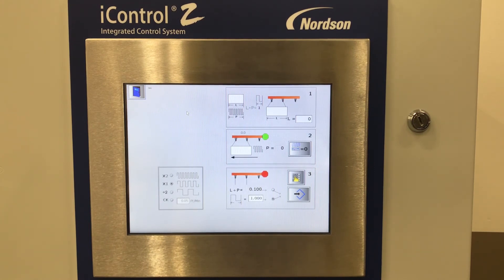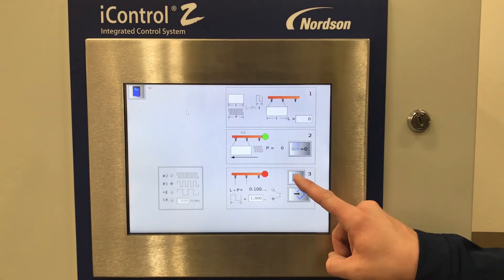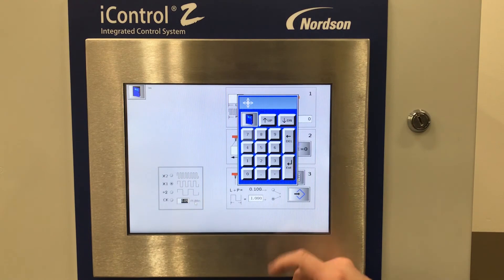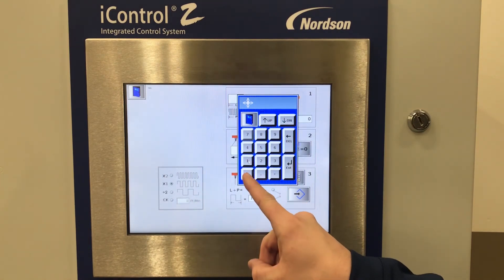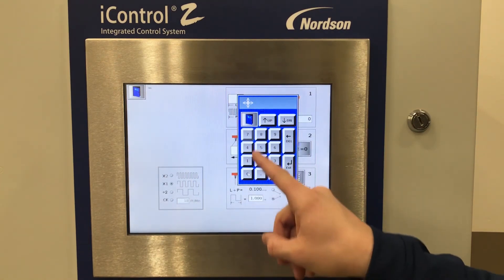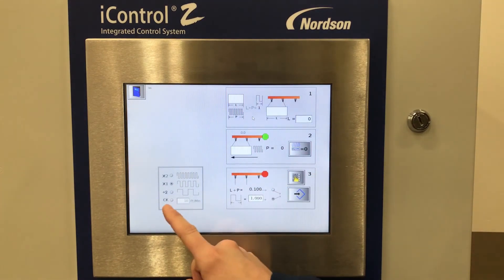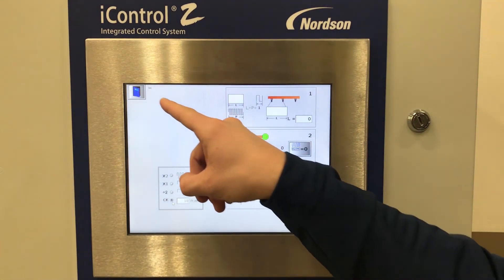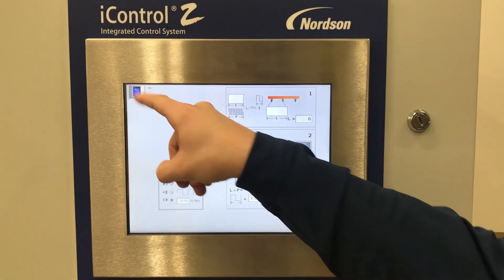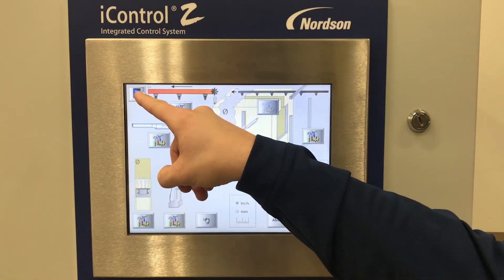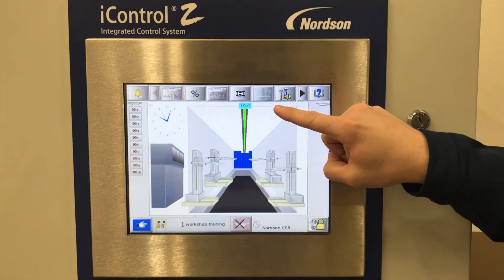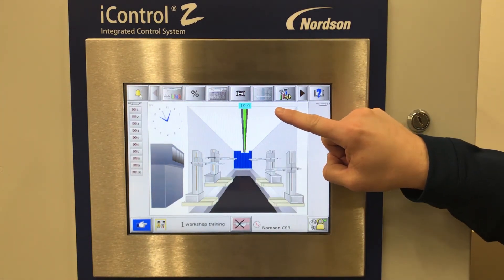For this setup, we're going to enter a conveyor speed of 10. Select the keypad on the right and then the text box for the CK mode. Highlight those numbers and enter 10. Close the window and select CK mode. Now close out of the conveyor configuration screen, close out of the tools configuration screen, and note that your line speed now reads at 10 feet per minute.